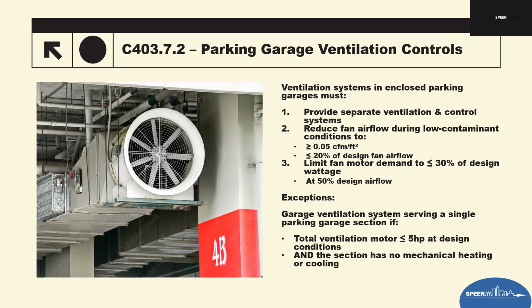Then, we have a separate system for each garage. So this first requirement is that each garage section must have its own ventilation system and its own control system. Same thing with HVAC systems. Each one needs to have their own thermostat. This allows ventilation to be controlled independently. So if one has a higher CO or NO2 levels, the other does not ramp up. Importantly, the code does not force you to divide a garage into multiple sections. It just says if the garage is divided, each section must have its own, not that you have to separate it.